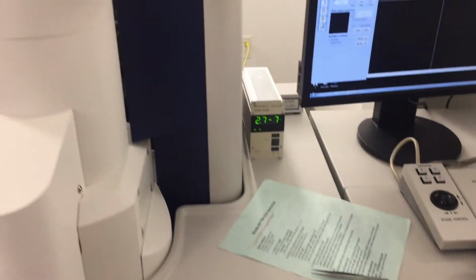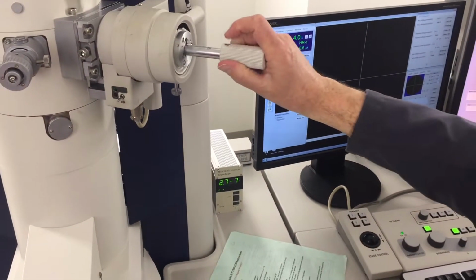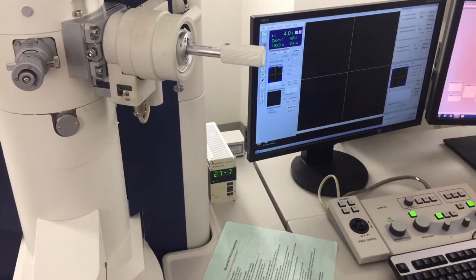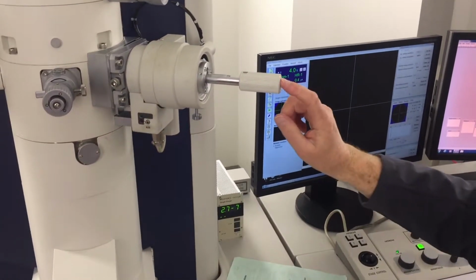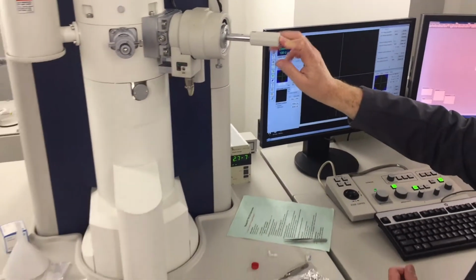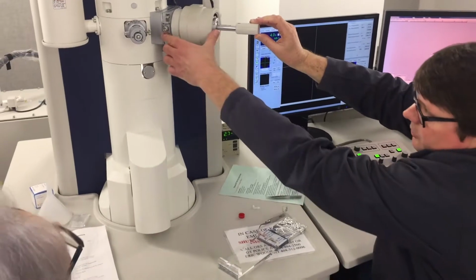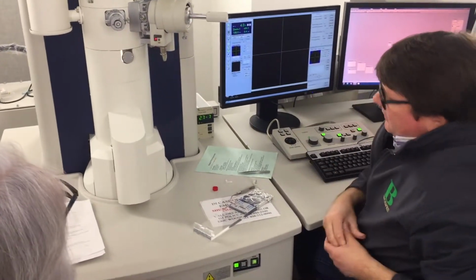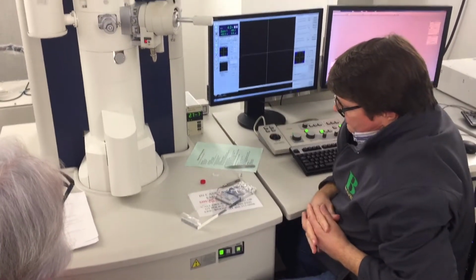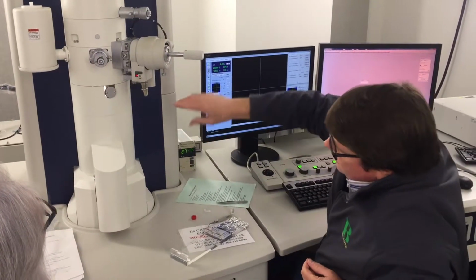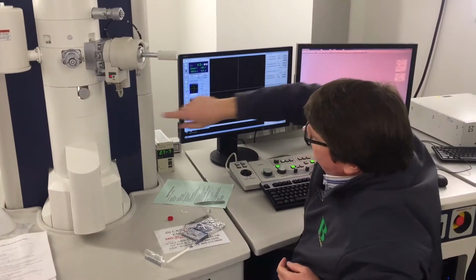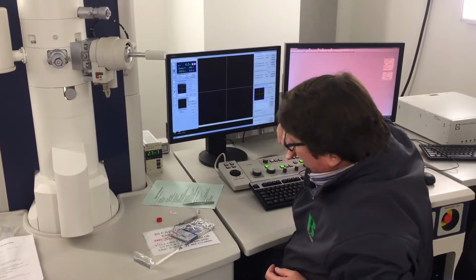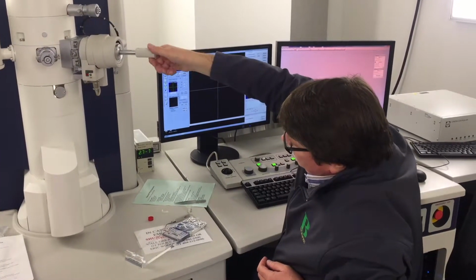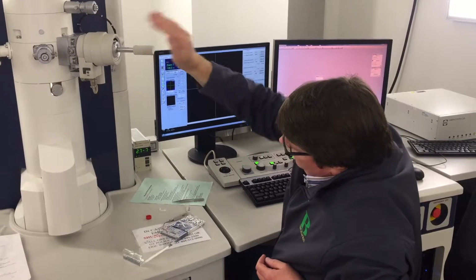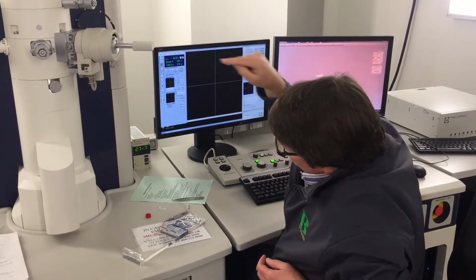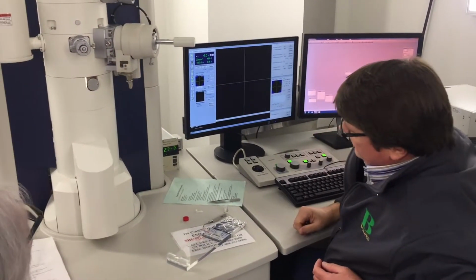And then I can load it into the stage. All of the microscope is under vacuum, so it's pumping down the small cylinder from atmosphere. And then when it reaches a high enough vacuum with the roughing pump that's over in the chase, I'll get a green light, and that'll allow me to turn the sample holder and open a ball valve that'll allow the sample holder to be inserted into the stage.